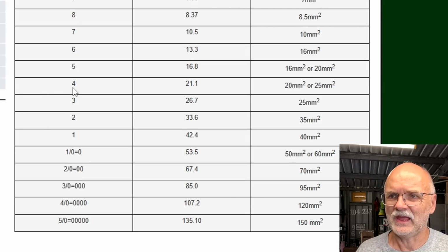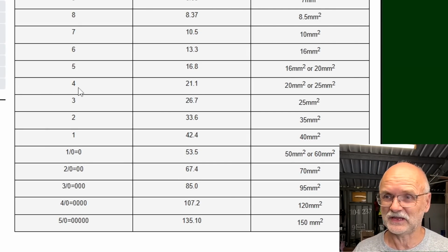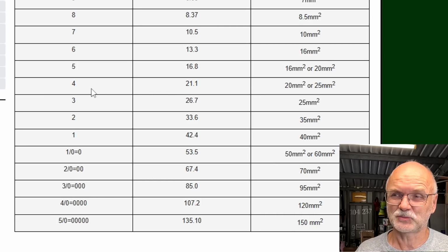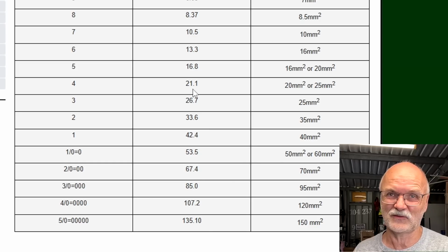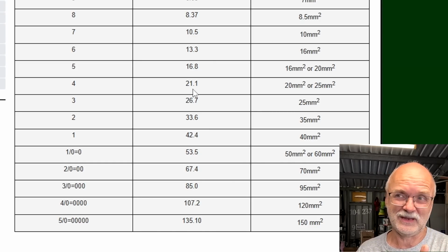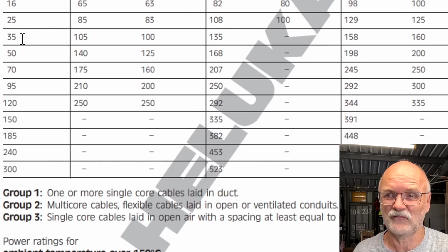Alright, we now have two 4-gauge wires in this battery. 4-gauge wire is 21.1 square millimeter, times 2 makes 42.2 square millimeter. So looking in the table for silicone cables here, we don't have a 42 square millimeter cable, we've got a 35 or a 50. It's larger than a 35, it's smaller than a 50.